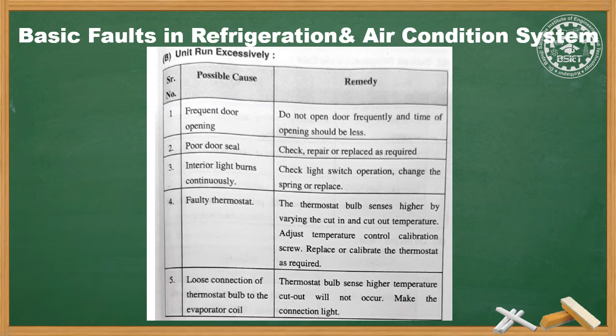Interior light burns continuously. Check the light switch operation, change the spring or replace. Faulty thermostat. The thermostat bulb senses higher by varying the cut in and cut out temperature. Adjust the temperature control calibration screw. Replace or calibrate the thermostat as required. Loose connection of thermostat bulb to evaporator coil. Make the connection tight.